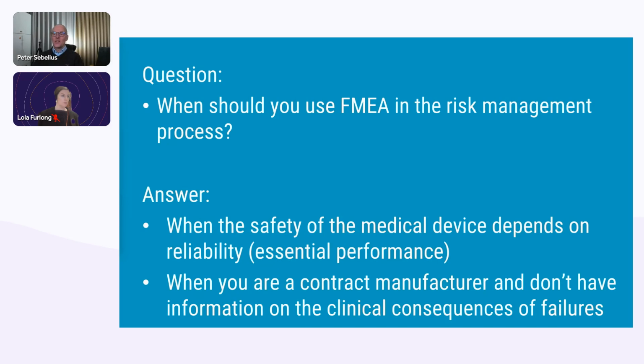So, when should you use FMEA in the risk management process? When the safety of the medical device depends on reliability, or if you have essential performance, it makes perfect sense. It's not required though, but it makes sense. If you're a contract manufacturer and you don't have information on the clinical consequences of failures, it also makes perfect sense to use FMEA, because then you can at least do something. Yes, so that is a potentially controversial topic. I'm hoping that we are going to get some feedback on that, and I can see there are lots of questions coming up here.